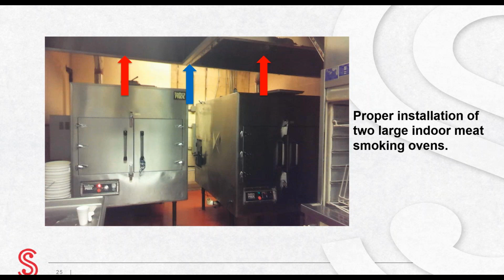The owner could have chosen to purchase one large exhaust hood and placed both ovens under it as long as only meat smoking ovens were under the exhaust hood. No other types of commercial cooking equipment can be under the hood, like griddles, grills, or fryers, and the exhaust system is served by a duct system separate from all other exhaust systems that meet NFPA 96 Type 1 requirements.